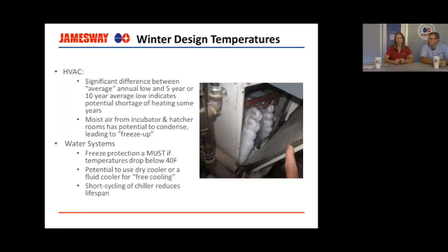You require freeze protection if your temperatures drop below 40 degrees Fahrenheit, drop below 0 degrees Celsius, through the use of glycol, whether that's a food grade ethylene or propylene glycol, that's really up to you as far as what you use, but you need a glycol in the system, and you need to have it actually freeze tested by the contractor that's adding it, and it needs to be checked regularly, because if you have a metering valve that's adding fresh city water into your water tank when the level gets a little bit low, that's going to be diluting your glycol and you can lose your freeze protection.